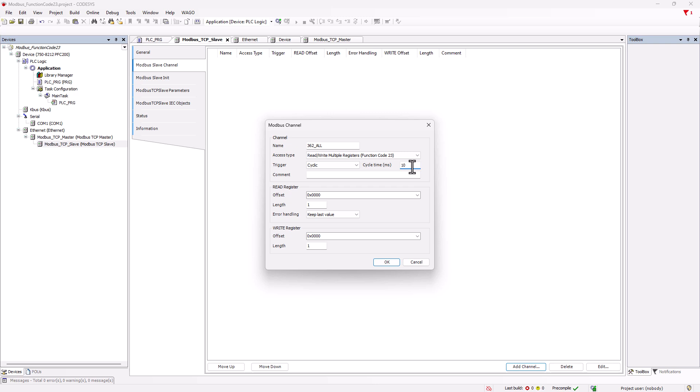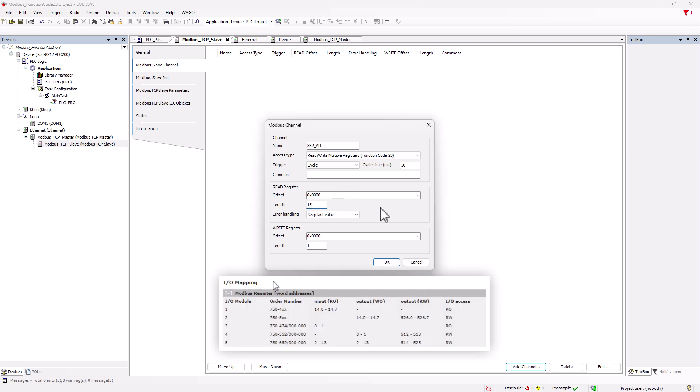Now, we enter the start address of the read register. In our case, it is 0. The length is 15 since the first analog input is at 0 and the last digital input is at 14.7. 0 to 14 are 15 words.